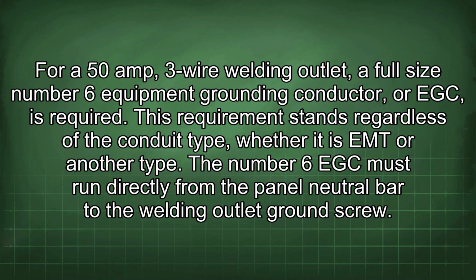For a 50 amp 3-wire welding outlet, a full-size number 6 equipment grounding conductor, or EGC, is required. This requirement stands regardless of the conduit type, whether it is EMT or another type. The number 6 EGC must run directly from the panel neutral bar to the welding outlet ground screw.